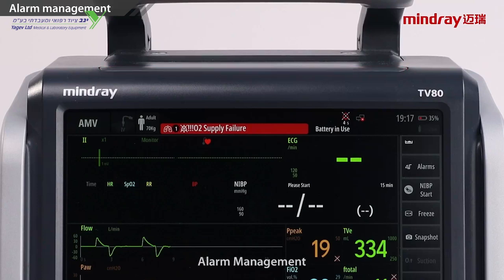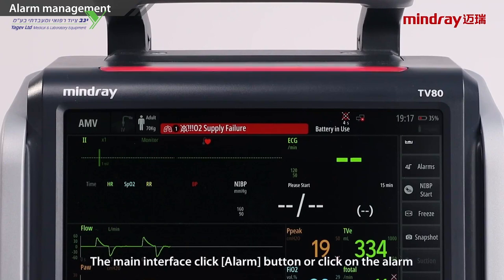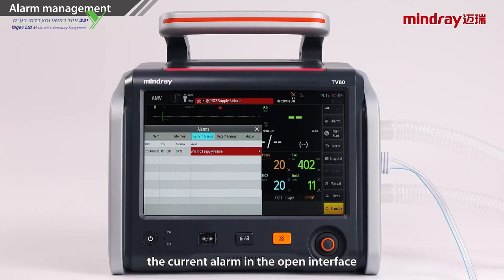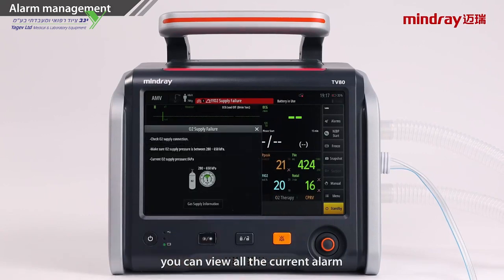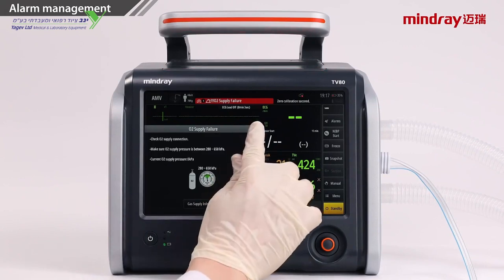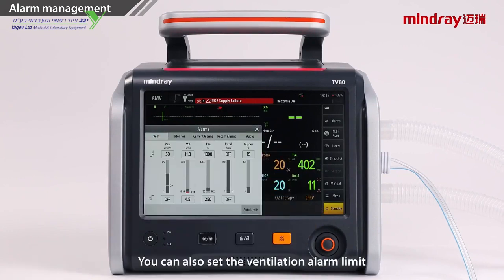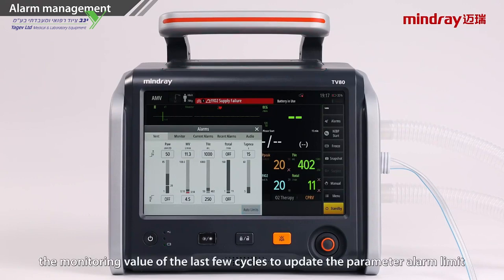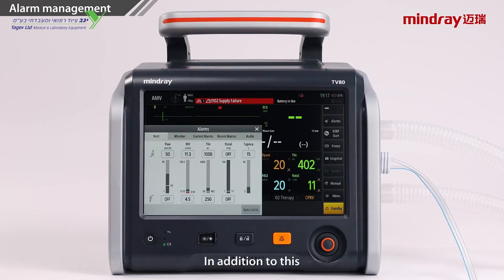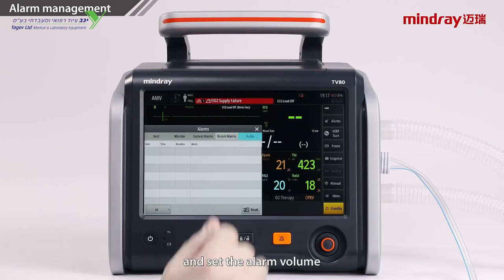Alarm management. The TV80 is accompanied by an alarm sound. On the main interface, click the Alarm button or click on the alarm itself. In the current alarm interface that opens, you can also view all the current alarms. You can also set the ventilation alarm limit. Click Auto Alarm Limit, and the monitoring values of the last few cycles will update the parameter alarm limits. In addition to this, you can view the recent alarms and set the alarm volume.